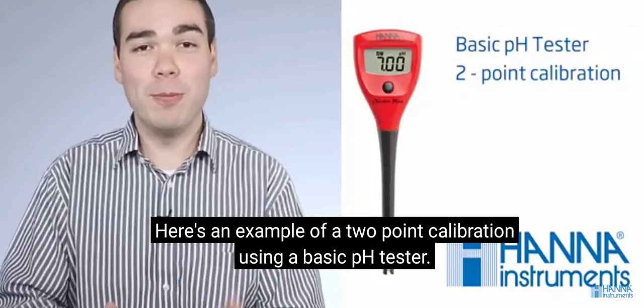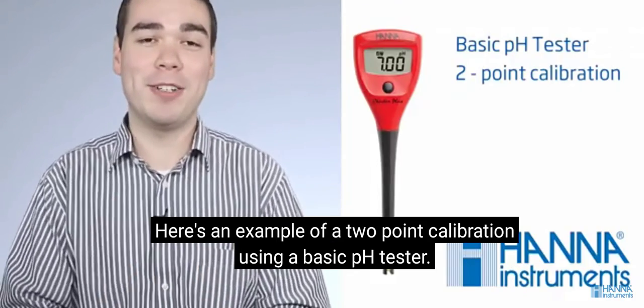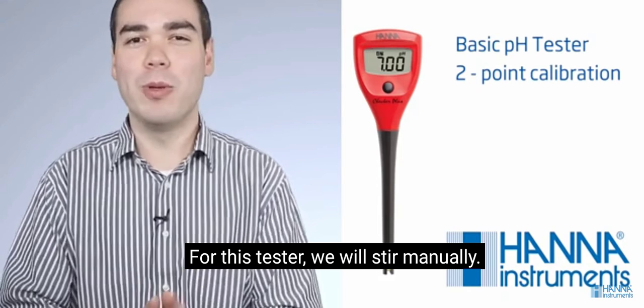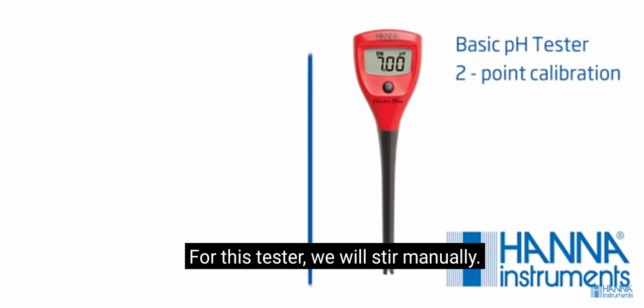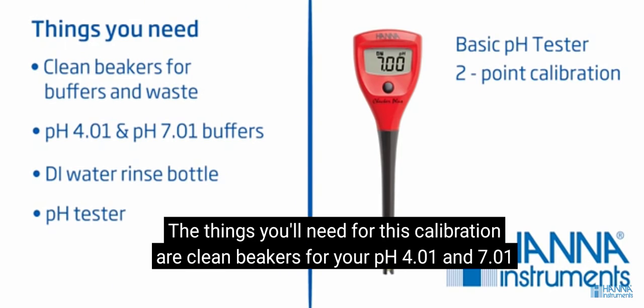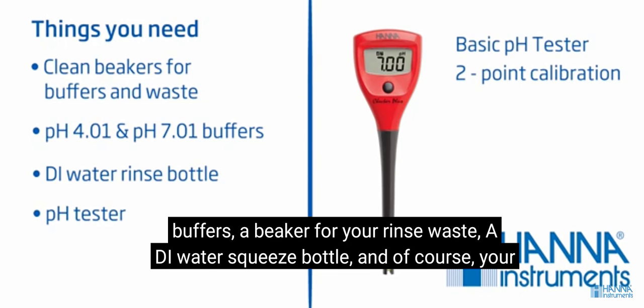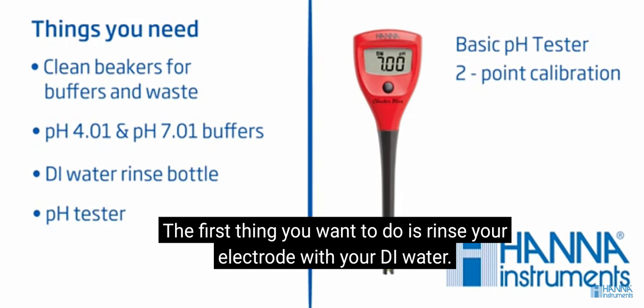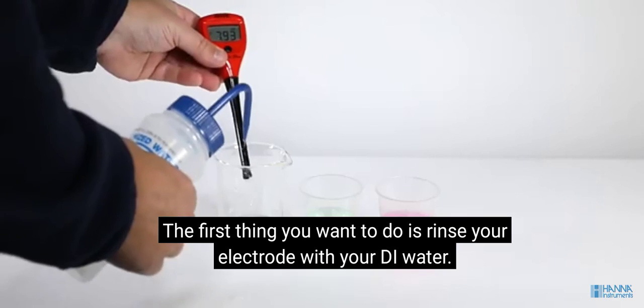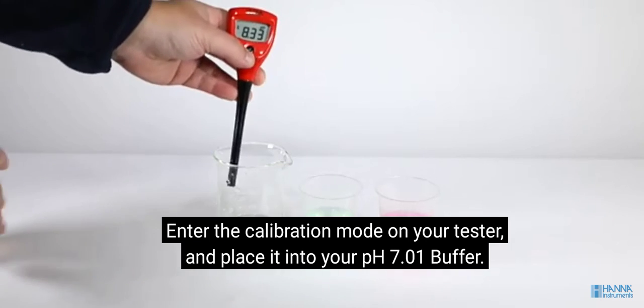Here's an example of a 2-point calibration using a basic pH tester. For this tester, we will stir manually. The things you'll need for this calibration are clean beakers for your pH 4.01 and 7.01 buffers, a beaker for your rinse waste, a DI water rinse bottle, and of course, your pH tester. The first thing you want to do is rinse your electrode with your DI water. Enter the calibration mode on your tester.